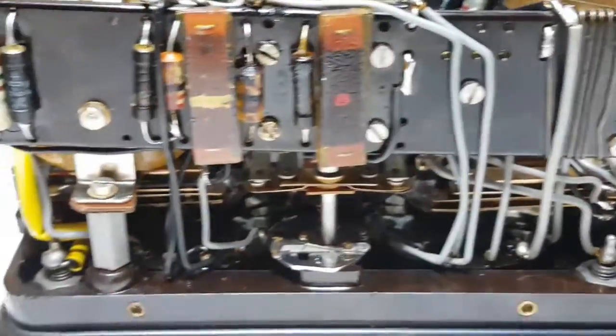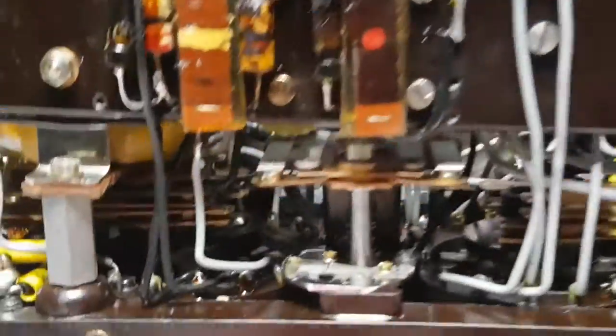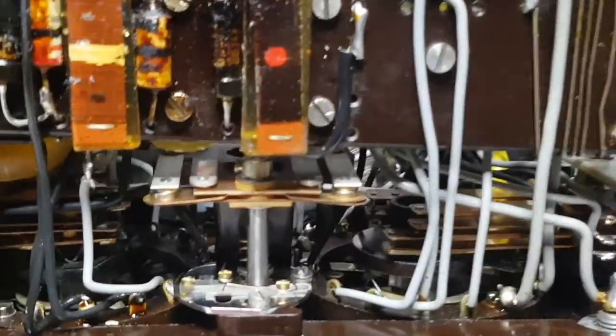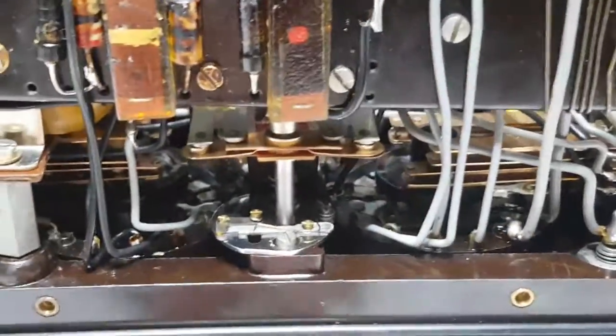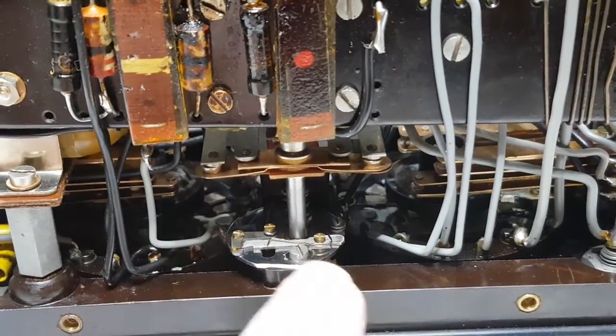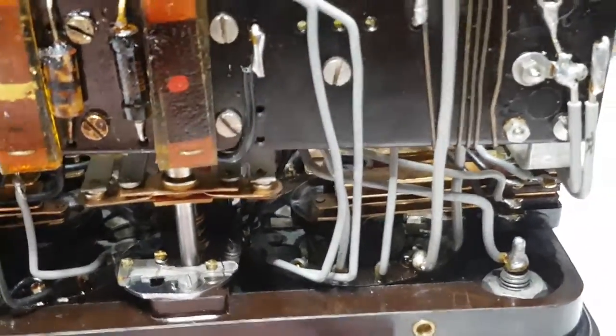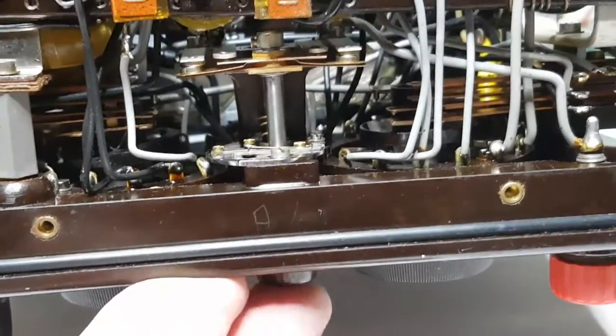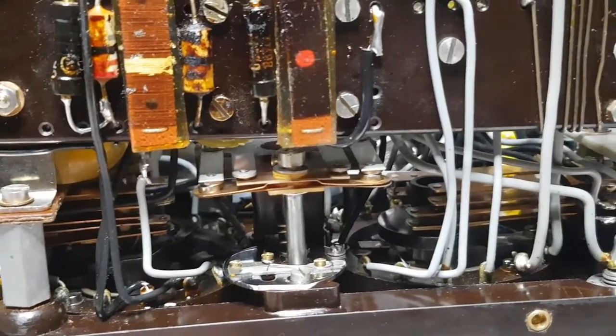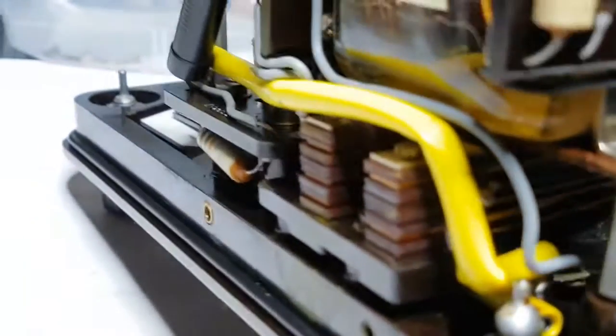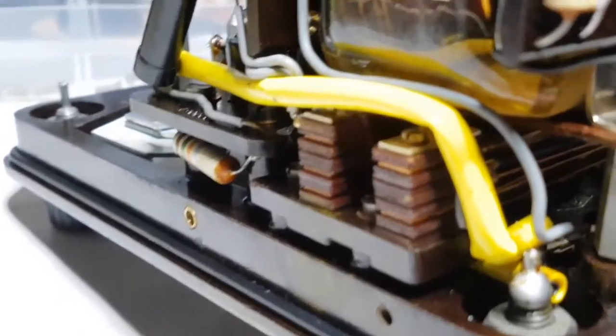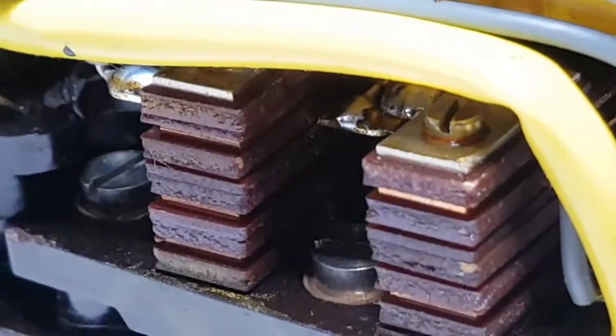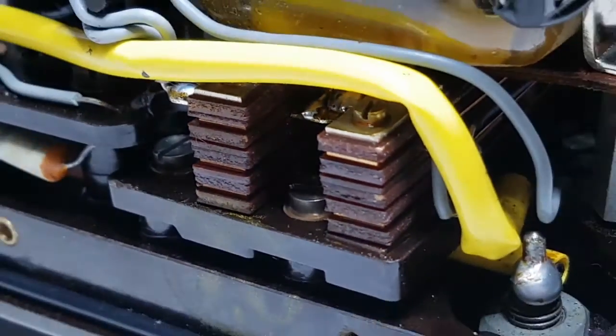That's a bit different underneath than the other one. Of course there is none on. I wonder if you can see the switches. And you've also got this, see this bottom button here? So it's all this mechanics. This bit here. I think that, not that but this, because there's a button here and it pops out if you overload it. It's like an overload trip device. It's on both of them. It actually has got some protection built in. I can't give you all off the top of my head at the minute but there is a few elements of protection.